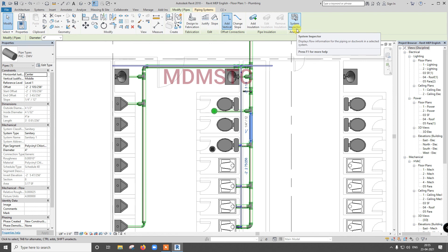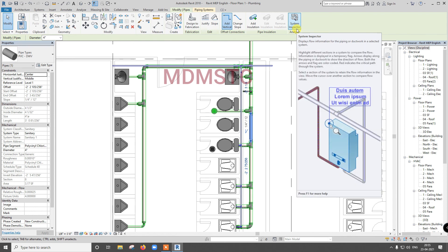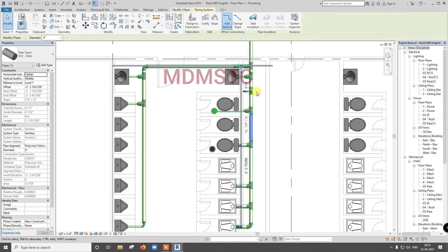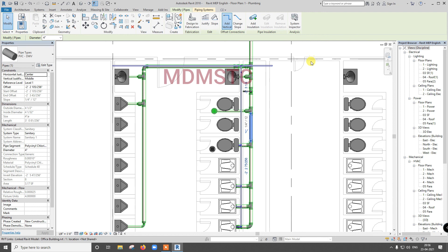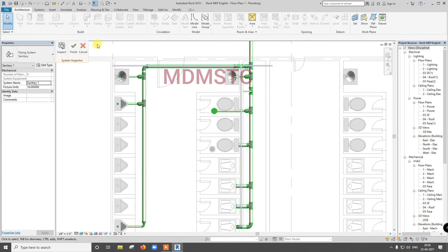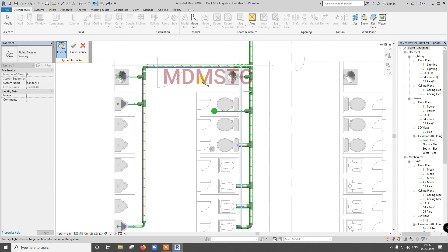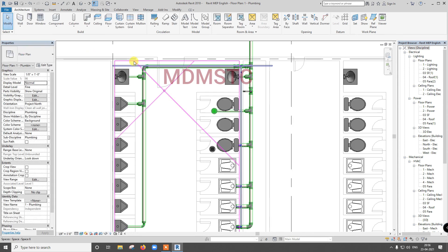For drainage, we need to calculate externally and select the size. System will not do the pipe sizing. It will not do the pipe sizing for drainage, only for water supply, that is pressure pipes only it will do. For gravity pipes it will not do. Just it will show system inspector, you can inspect the flow direction.